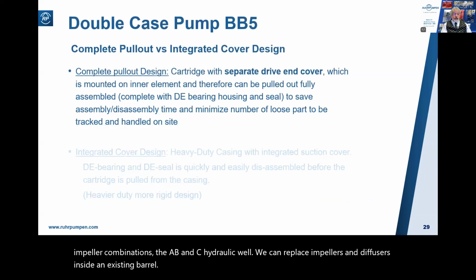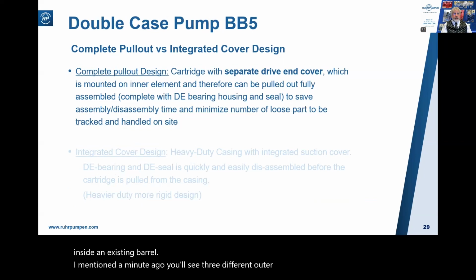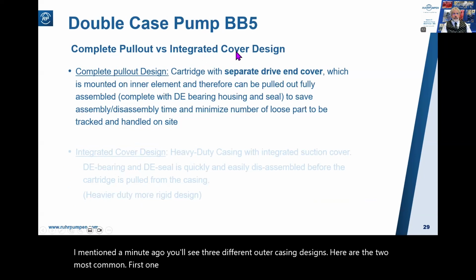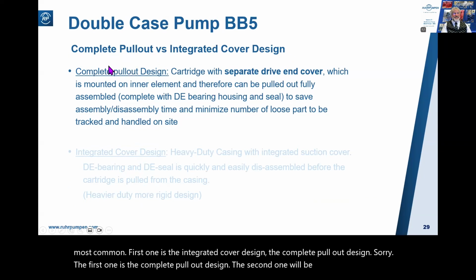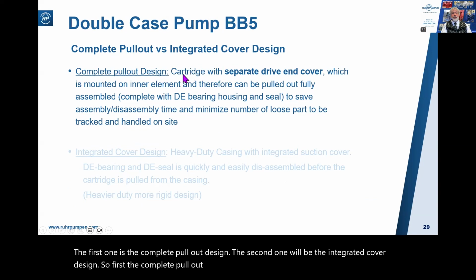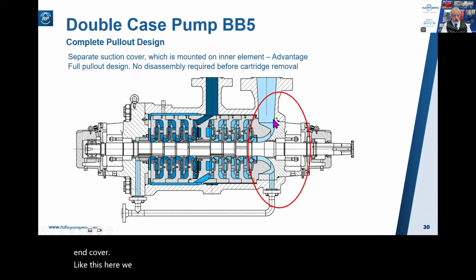Now, I mentioned a minute ago, you'll see 3 different outer casing designs. Here are the 2 most common. Sorry, the first one is the complete pull-out design. The second one will be the integrated cover design. So first, the complete pull-out design, which is the cartridge having a separate drive end cover, like this. Here we see the cover forging is a separate forging or casting from the outer case, with an O-ring there to seal it.